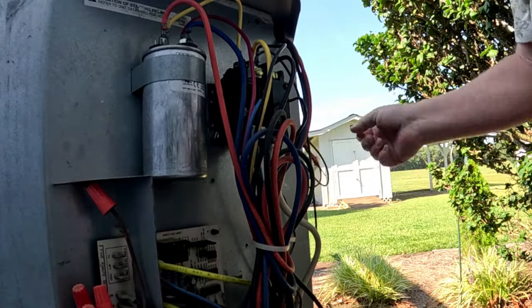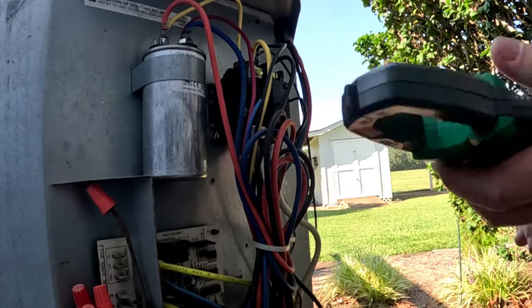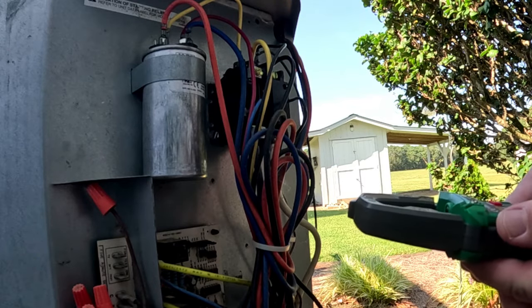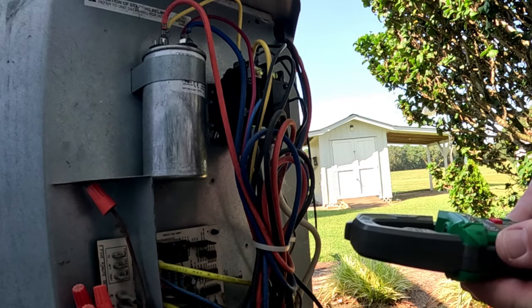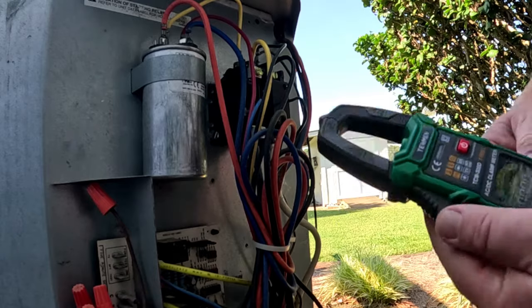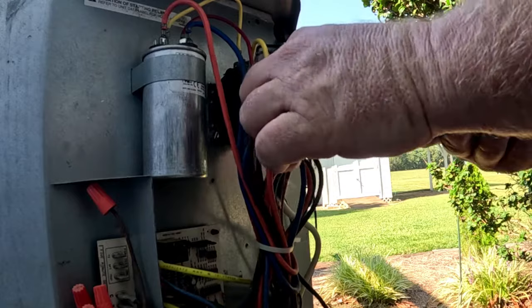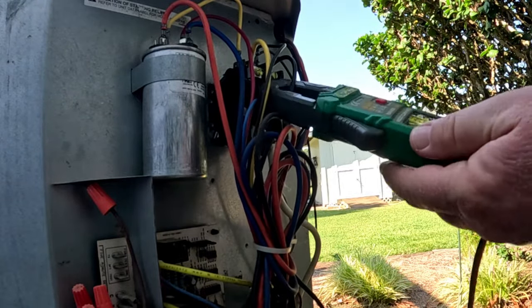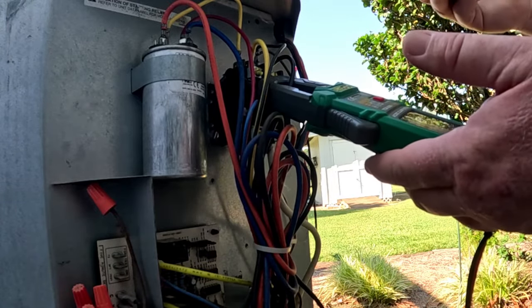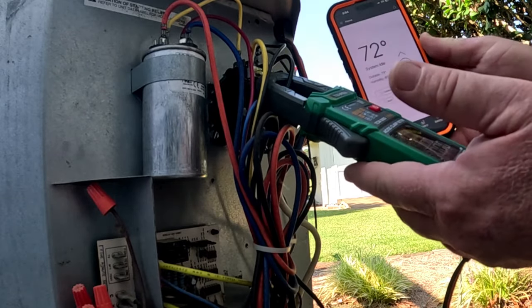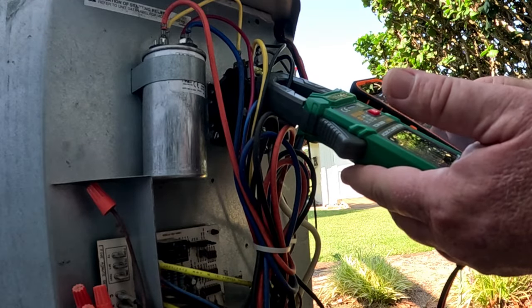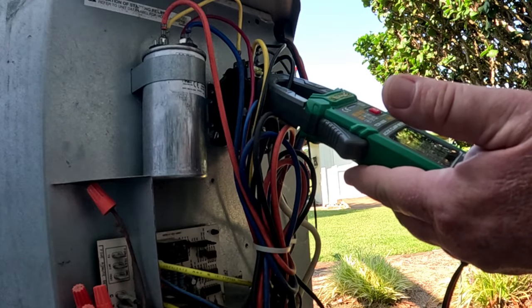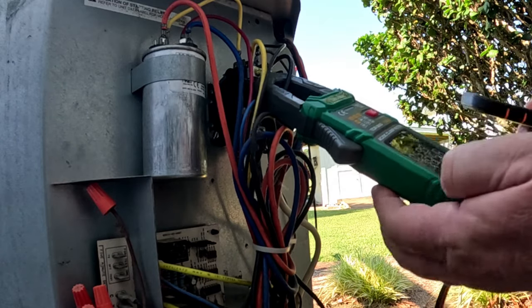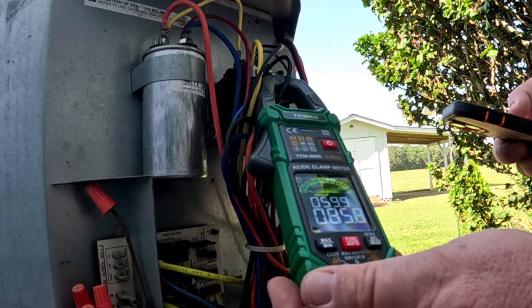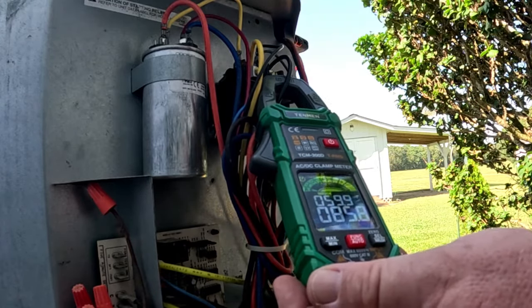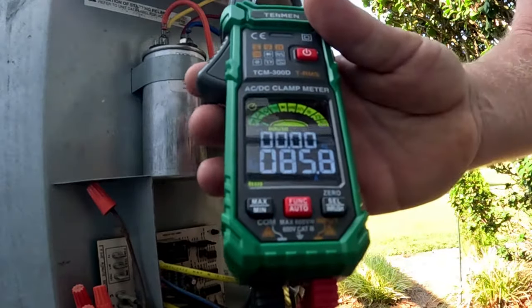So now let's check this amp draw accuracy, and we're going to start with our inrush function. I'm going to turn this on and see what happens. So we're going to set this to amps. We're going to set it for inrush, and then we're going to get around our common for our compressor, and then I'm going to turn this thing on real quick through my app. Gives me an inrush of 85. So I'm going to turn it back off.